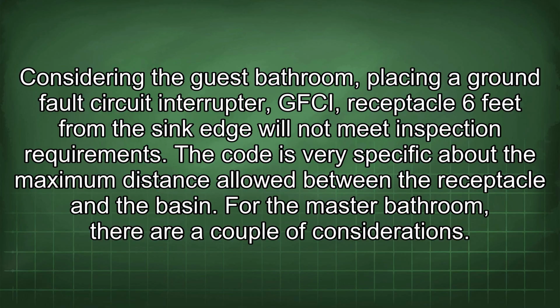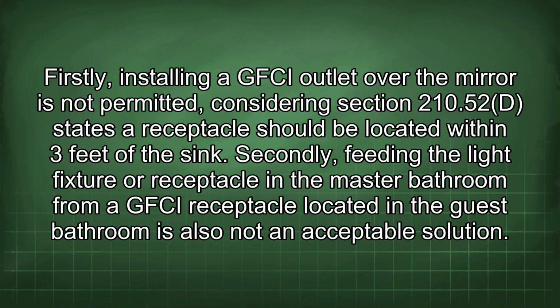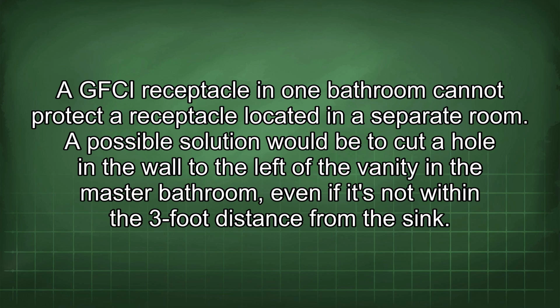For the master bathroom, there are a couple of considerations. Firstly, installing a GFCI outlet over the mirror is not permitted, considering Section 210.52(D) states a receptacle should be located within 3 feet of the sink. Secondly, feeding the light fixture or receptacle in the master bathroom from a GFCI receptacle located in the guest bathroom is also not an acceptable solution. A GFCI receptacle in one bathroom cannot protect a receptacle located in a separate room.